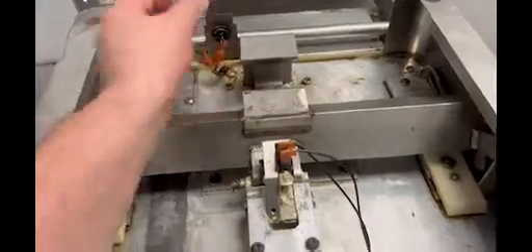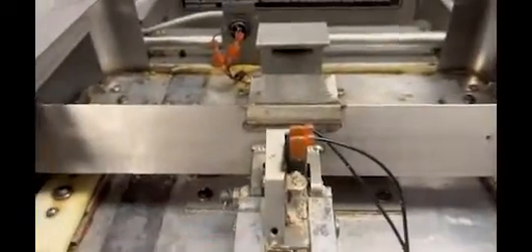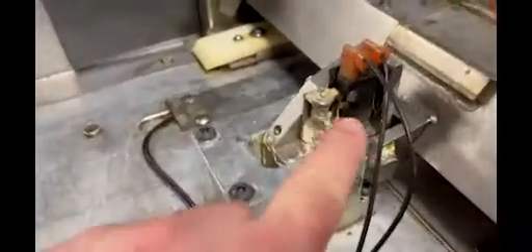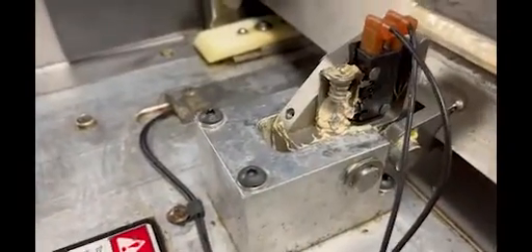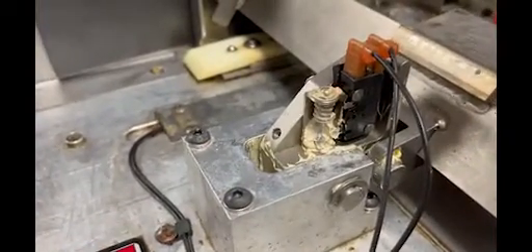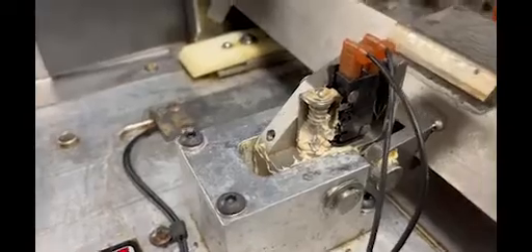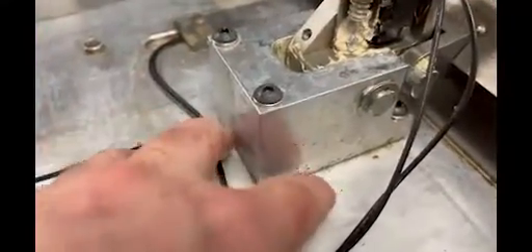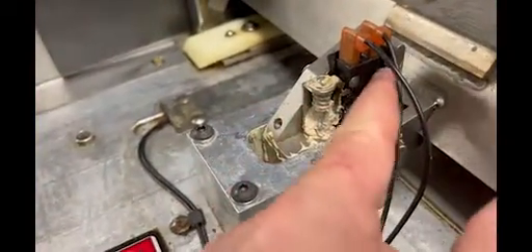Now if that doesn't work, I want to look at this switch right here itself, because whether I have an E84C or E84D error code, this switch can be going bad. What's happening is the pin inside here is fine, it's pressing up on this, but it's not opening or closing the line in here.